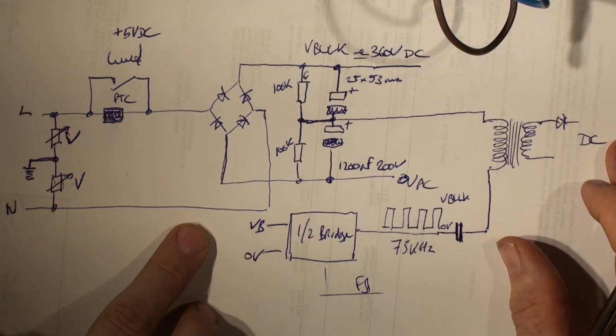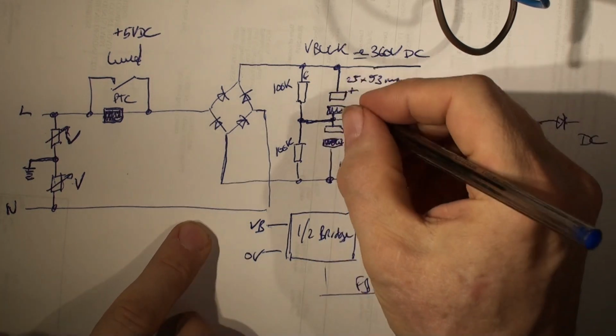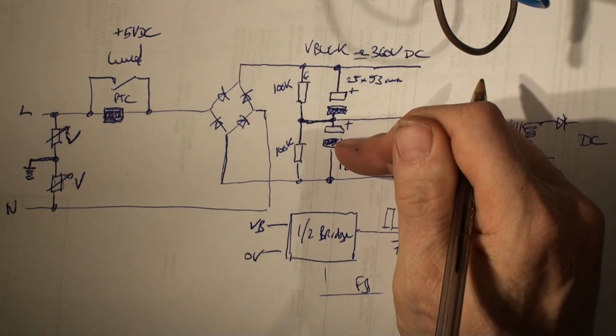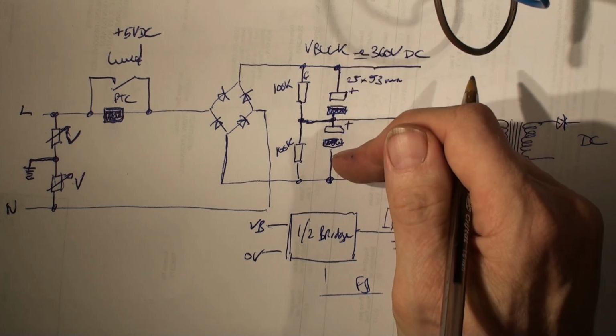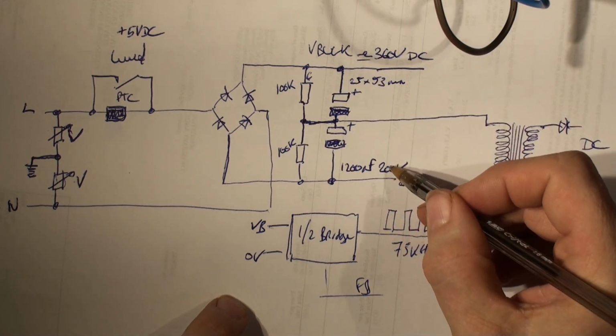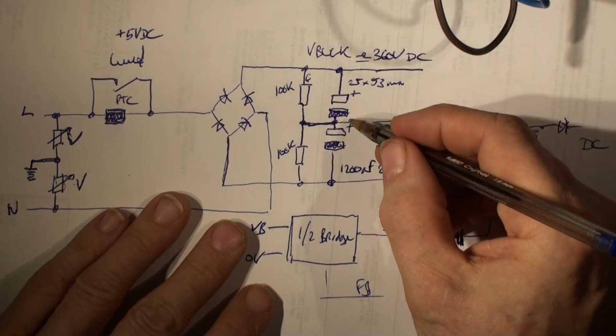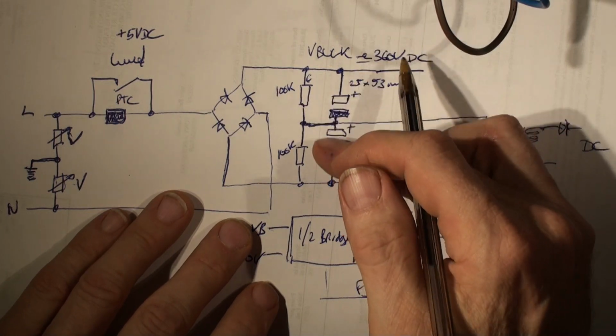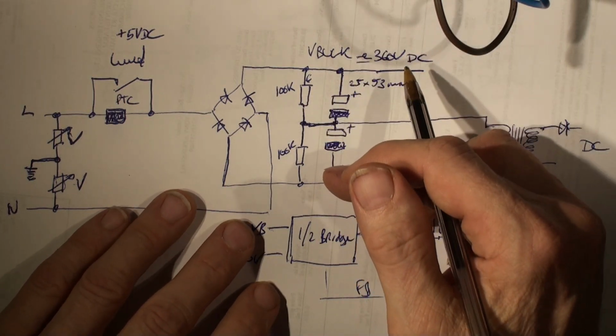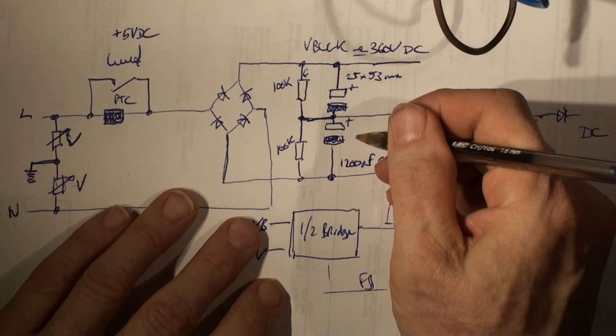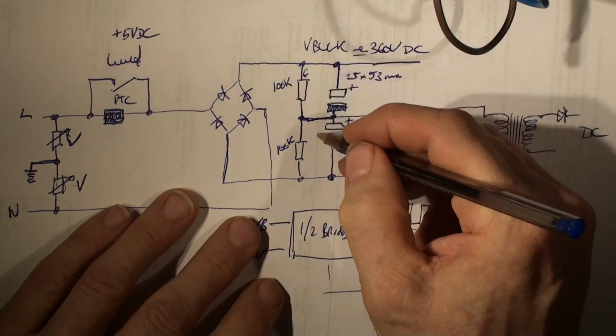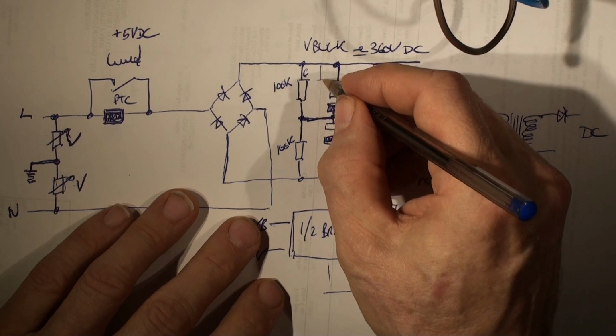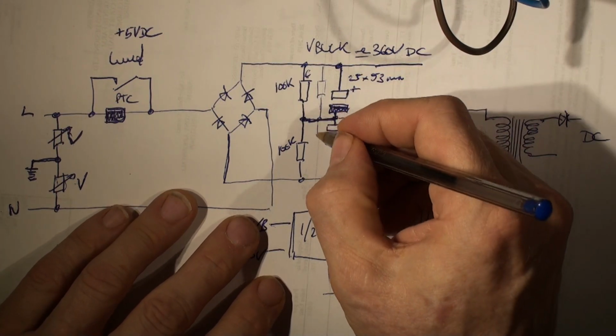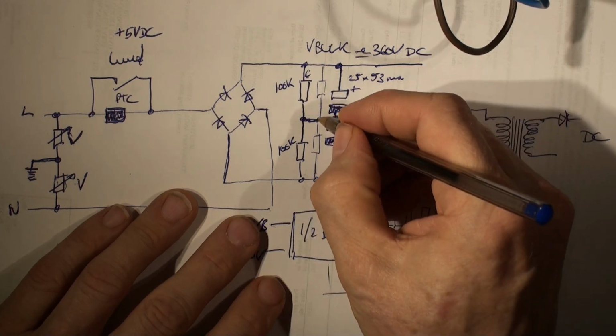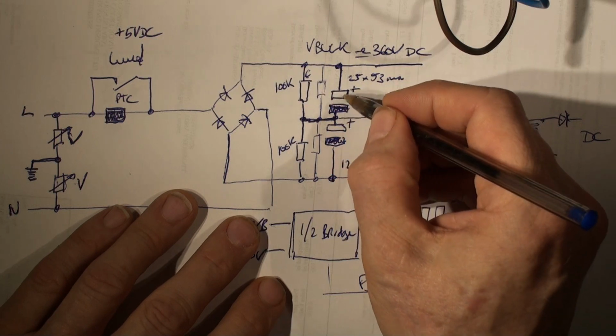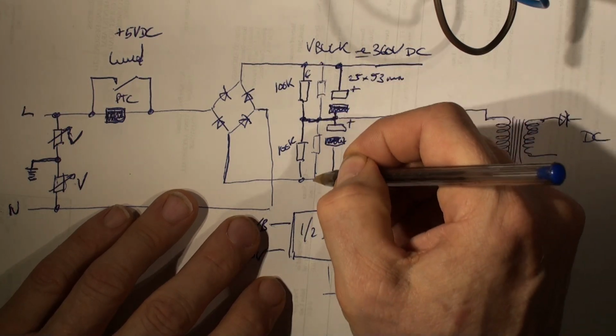That's the circuit you've got. Now all sorts of things can happen with this. You can have a minor leak in your capacitor so these become out of balance—bearing in mind these are 1200 microfarad, 200 volts, and the leakage should only be in the order of microamps, maybe 1 or 2 microamps. But if one's leaking 3 microamps and the other 1 microamp, this DC voltage network effectively introduces a parasitic resistor representing the leakage impedance of that capacitor at mains voltage.